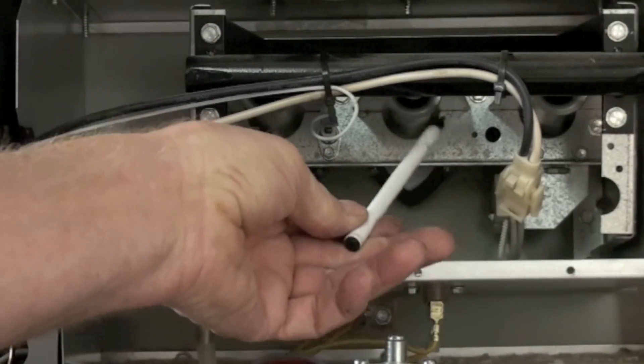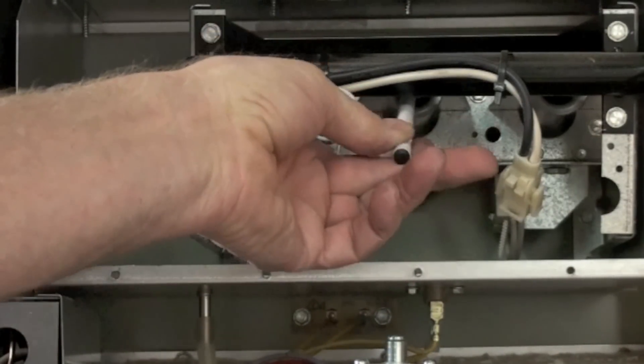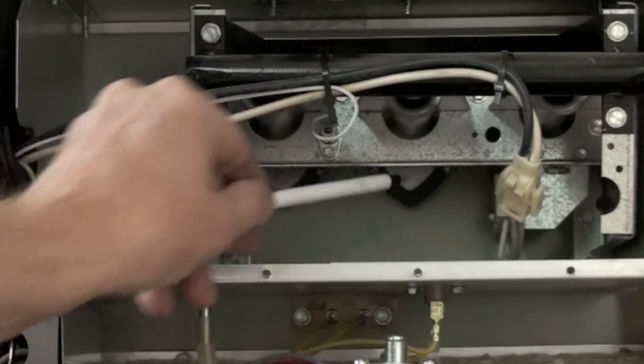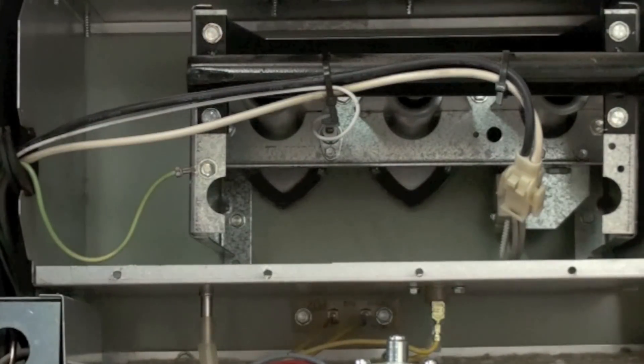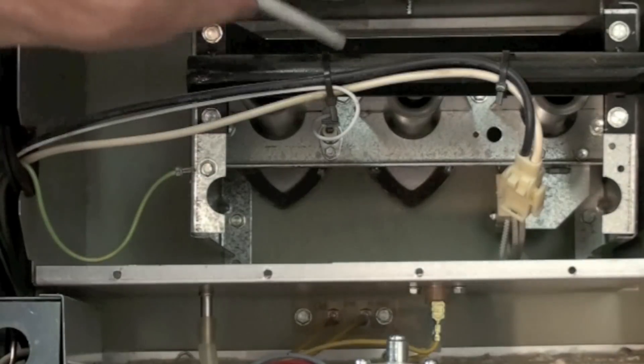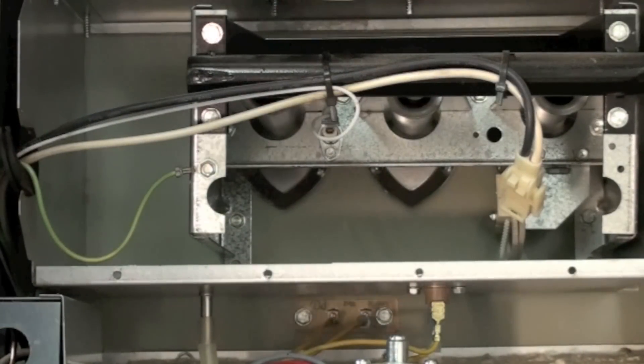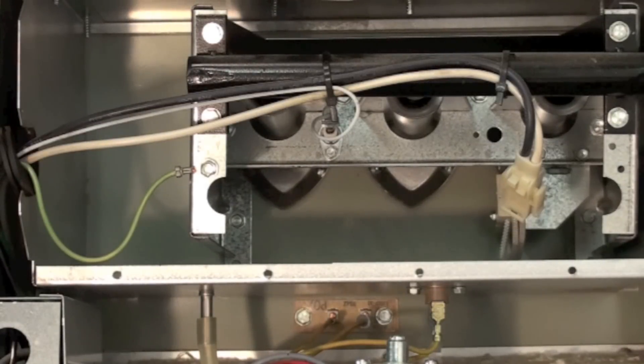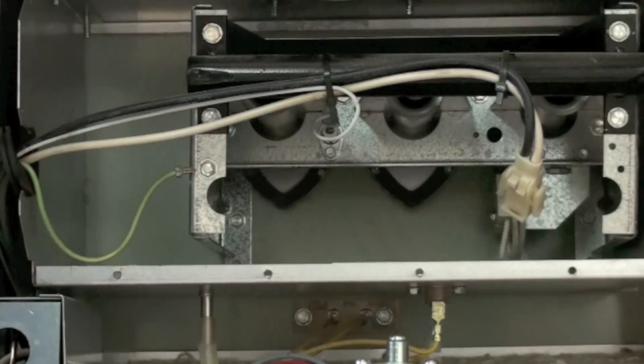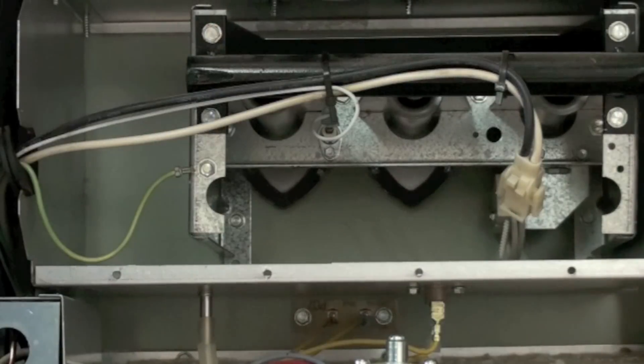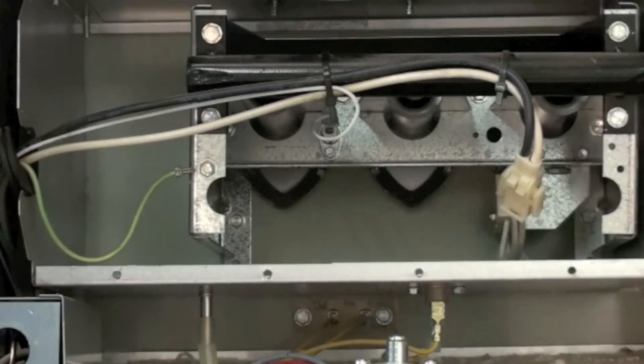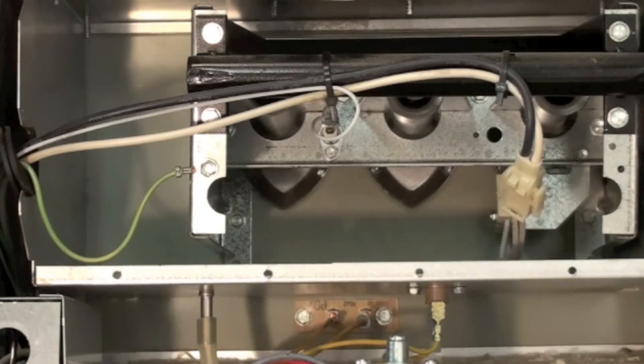Virtually everything now is inshot burners. The flame should be going straight into there and straight into the heat exchanger. If it's not, if it's rolling up to this top here or something like that, you could very well have a heat exchanger problem. It usually gets worse when the fan motor starts. But that could cause a short cycle. And that's pretty bad news. You get that fixed.